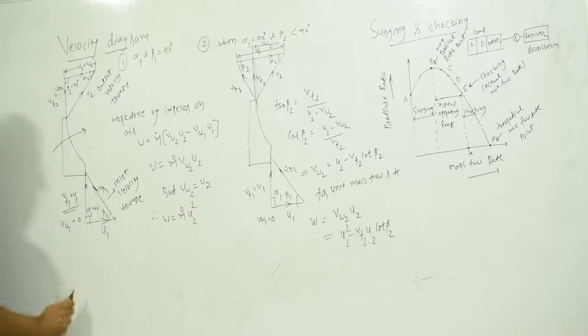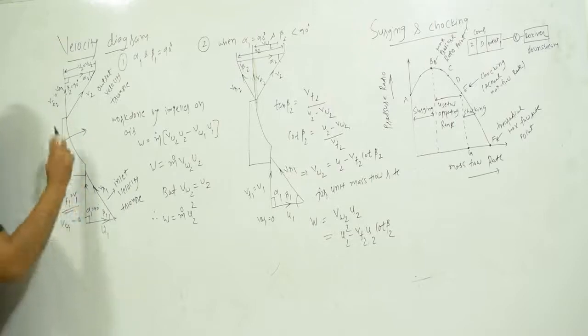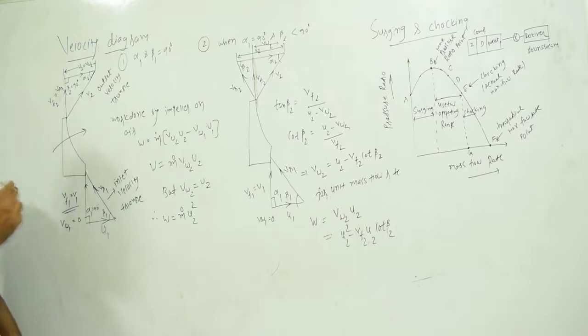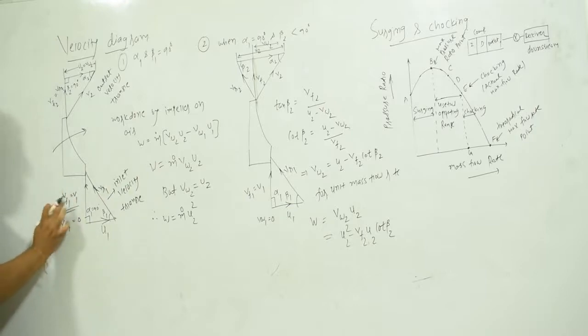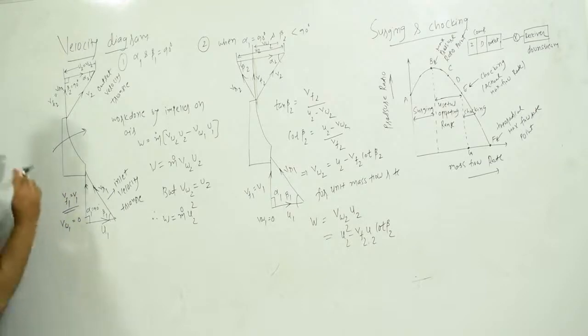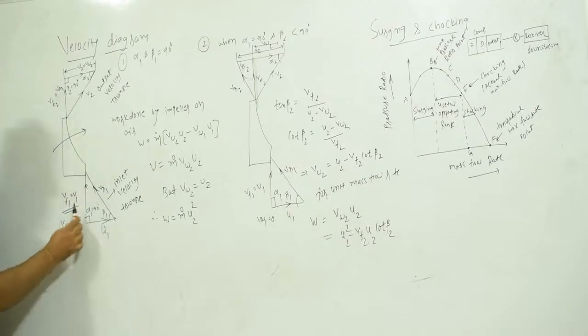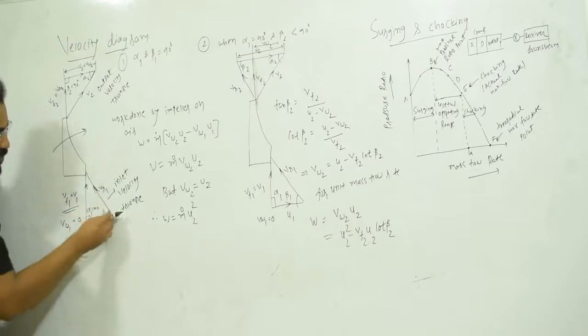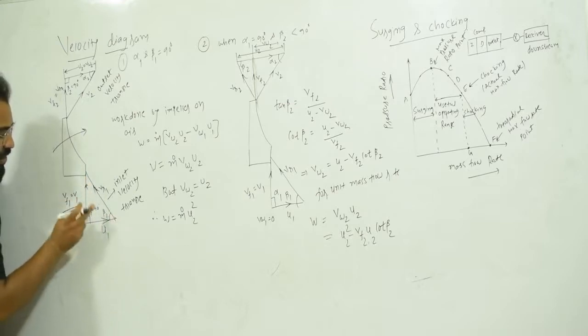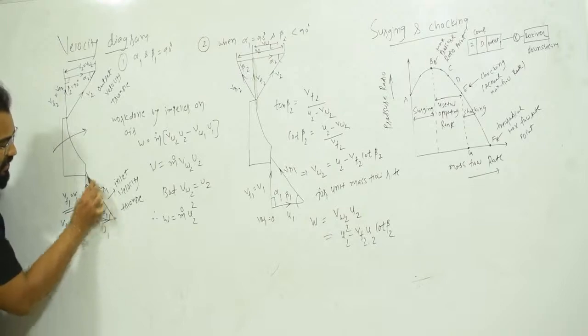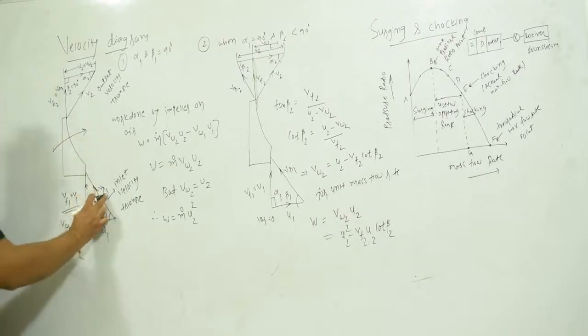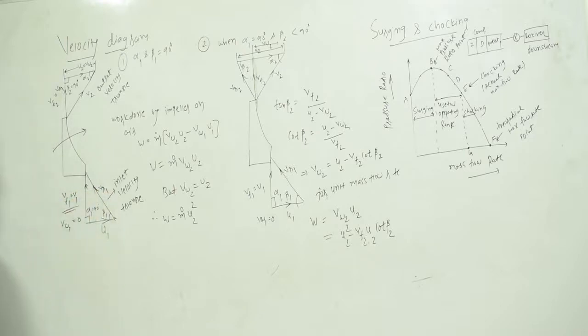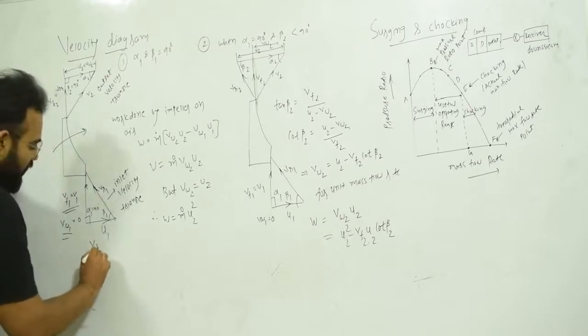Because in a centrifugal compressor the fluid enters axially, v1 equals vf1. Always remember that v1 is the resultant of u1 and vr1. So with u1 and v1 known, we are left with vr1, which we draw to complete the triangle. vr1 is the relative velocity, and vw1 is the whirl velocity.